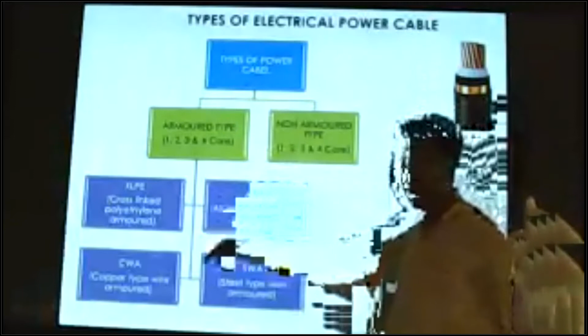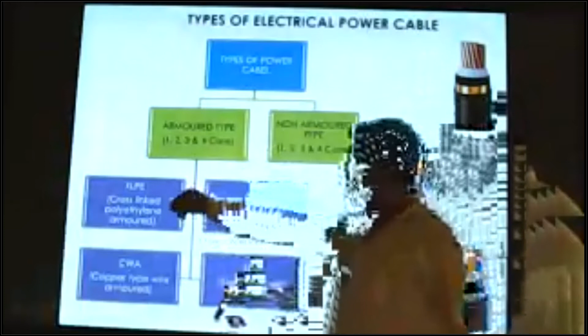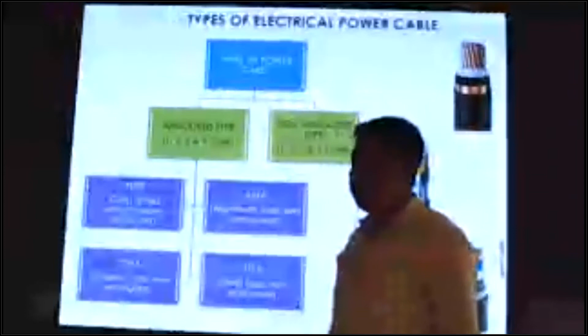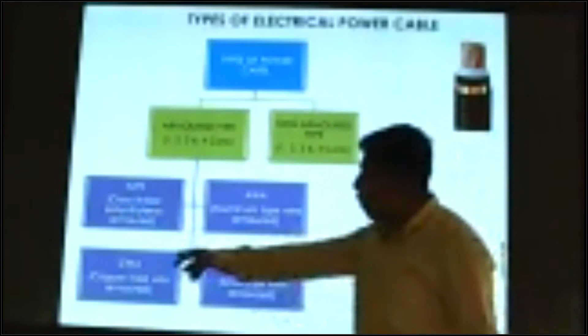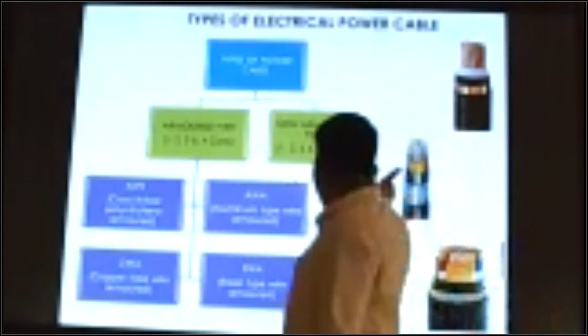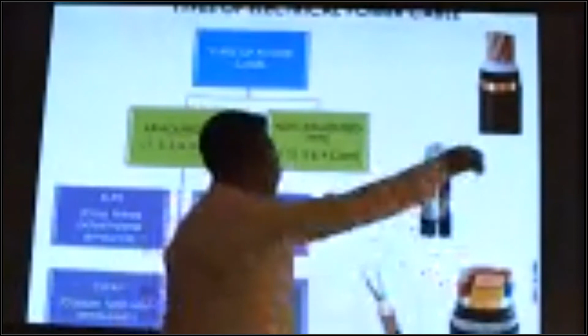Okay. Inside the armor cable we have 4 types of armor. Very important, this one. XLP type, AWA type, CWA type, SWA type. So what is the full form of XLP? Cross-linked polyethylene. And AWA, aluminum wire armor. CWA, copper wire armor. SWA, steel wire armor. So all the types of armor cable are available here.